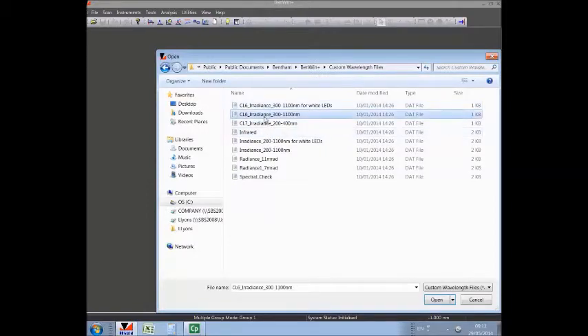For the CL6 calibration, there are two, both covering the range 300 to 1100 nanometers, which is the base range of this irradiance measurement with the CL6, the D7 diffuser, and the IDR300. The CL6 irradiance 300 to 1100 steps 2 nanometers to 400 nanometers, then 5 nanometers thereafter.